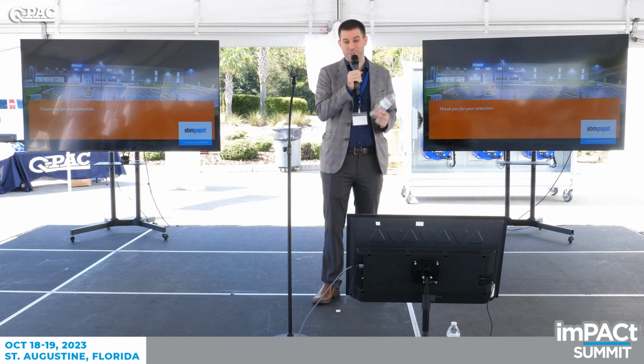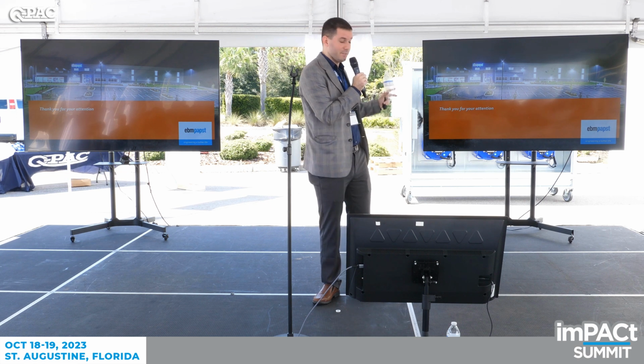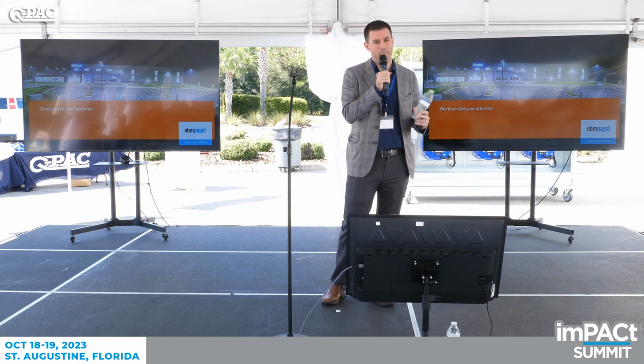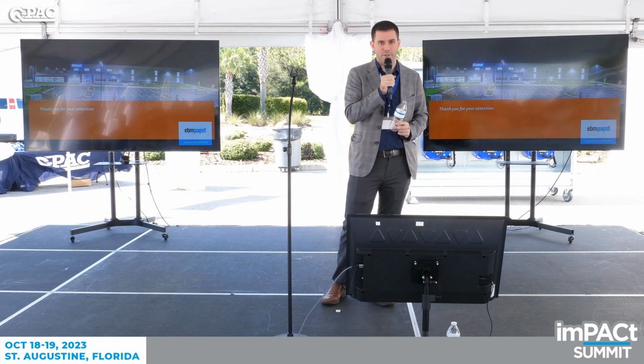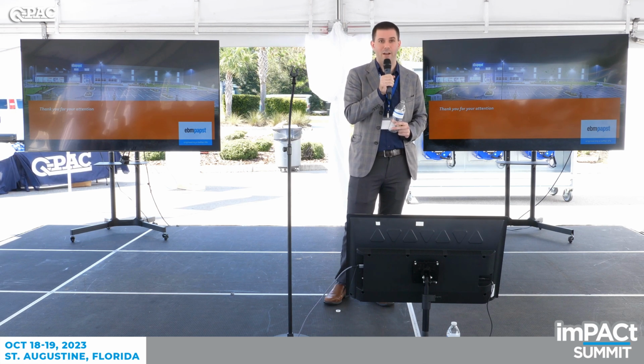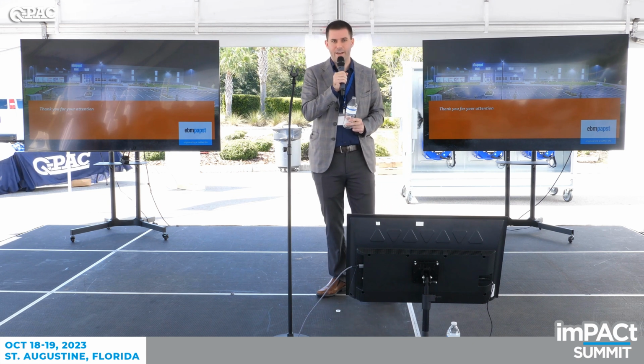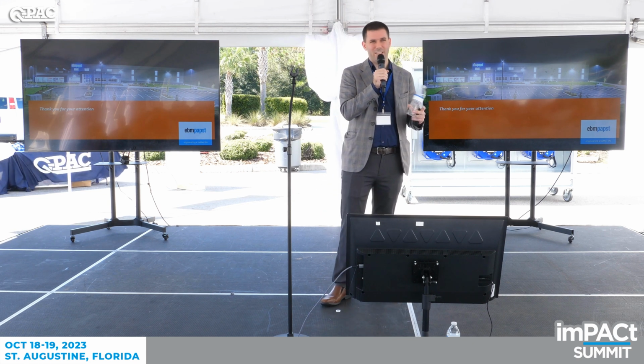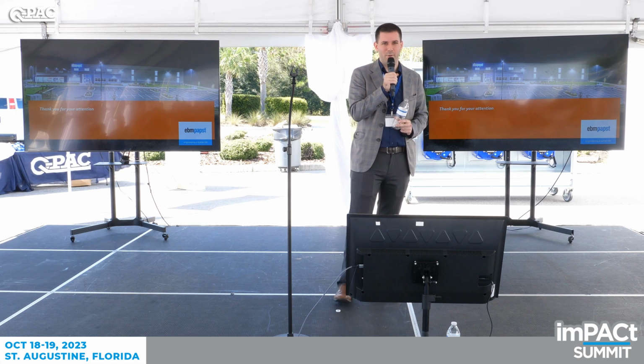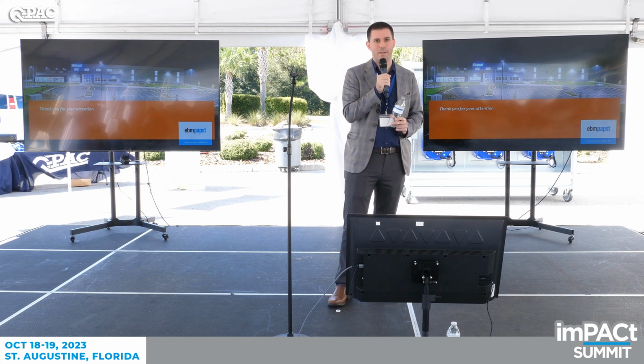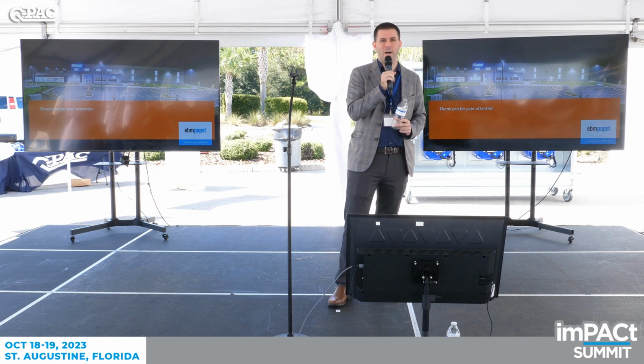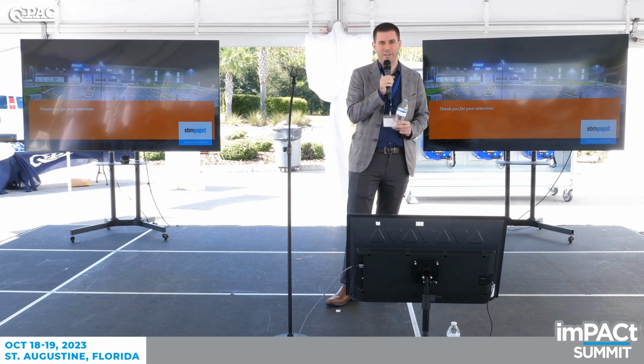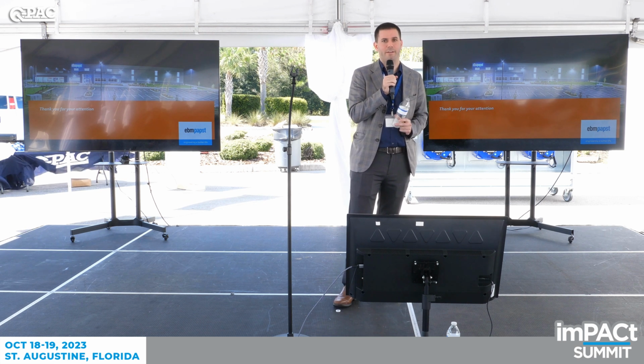Some of these fans are rated, like that condenser fan I showed the video of, to be outdoor 24/7. So in rain, in very, very high humid condensing environments, that's fine. In an air handler, normally I think we can get up to like 98% humidity. So it's fine to be in a humid environment, as long as you don't have too much condensation in an air handler, but the fan itself can handle it.